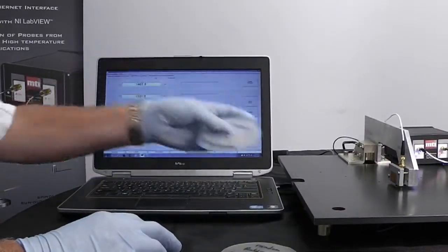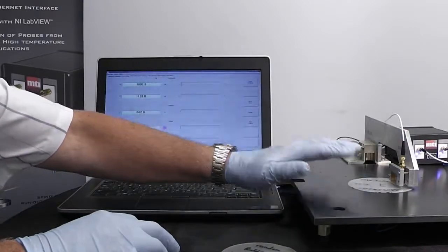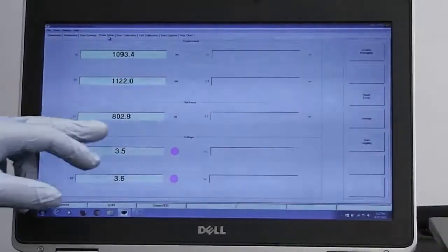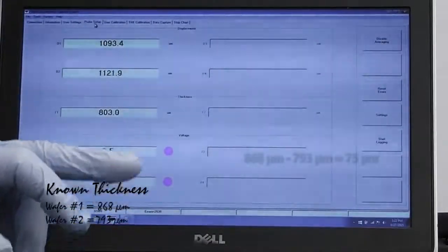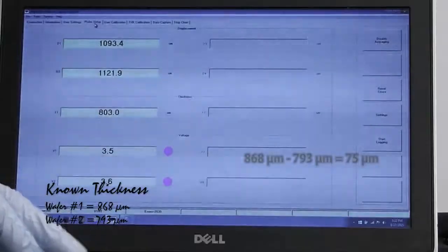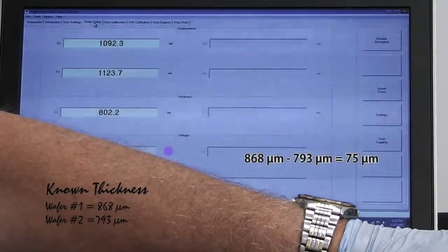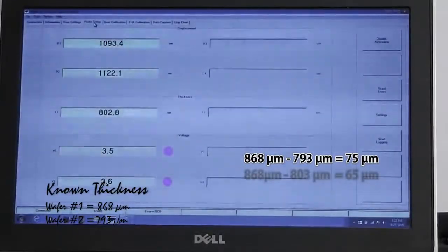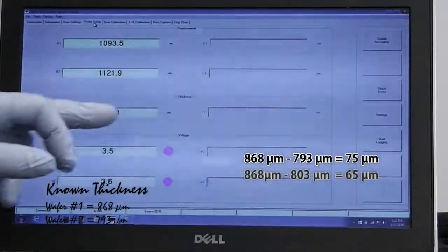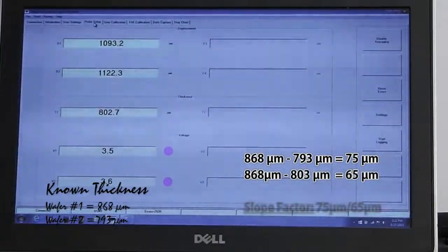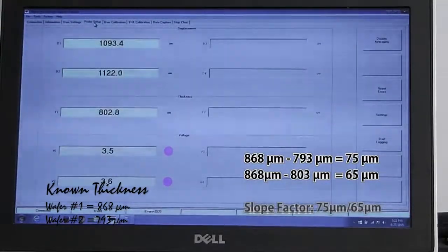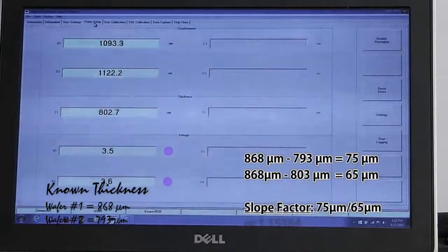The next thing we're going to do, we're going to take our second wafer which is 793, slide that between the probes and then we're going to measure what the reading is here. We know the difference between the two probes is 868 minus 793, we know the absolute delta difference. And then what we do is we take the difference between what the wafer actually is versus what is showing here. So we divide the difference between the known thickness by the apparent thickness and that gives us our new slope factor.